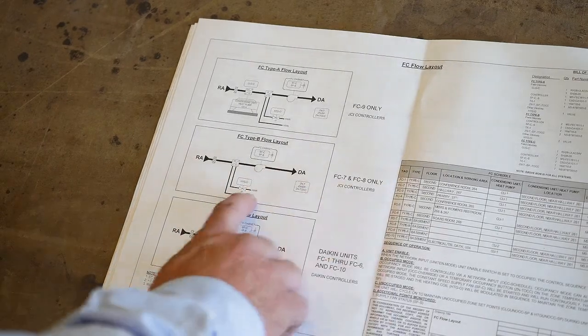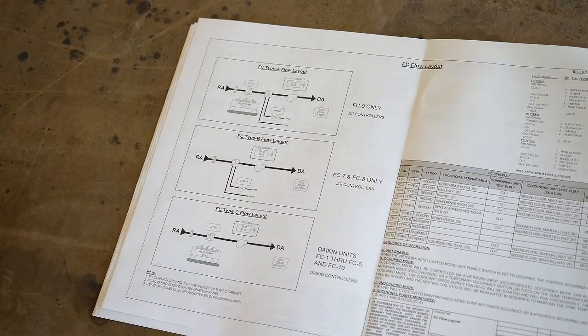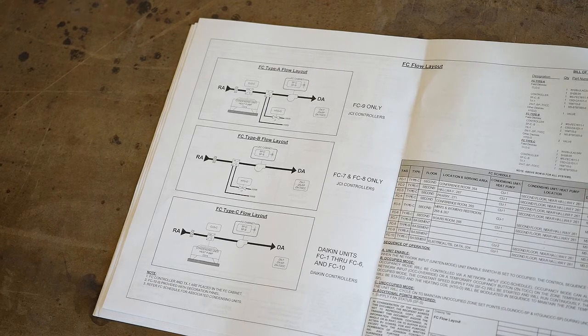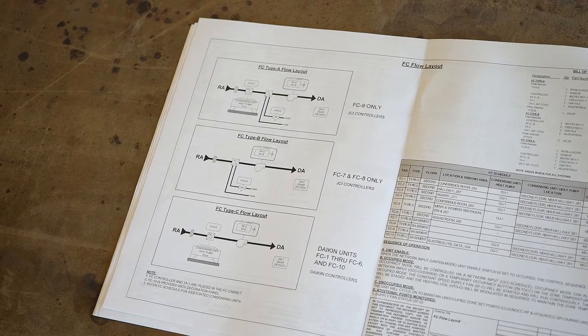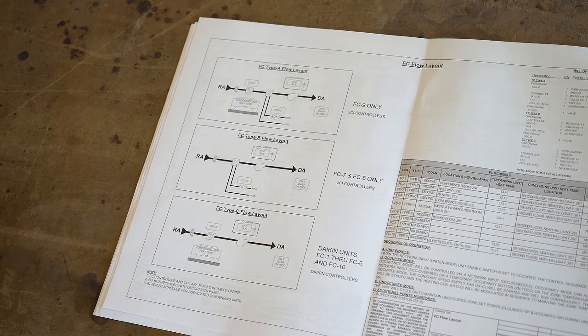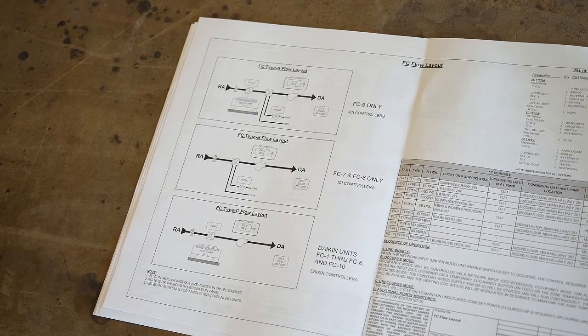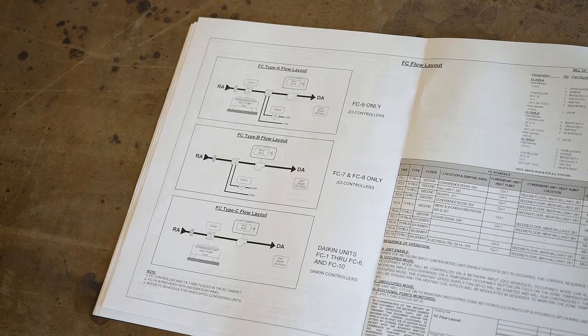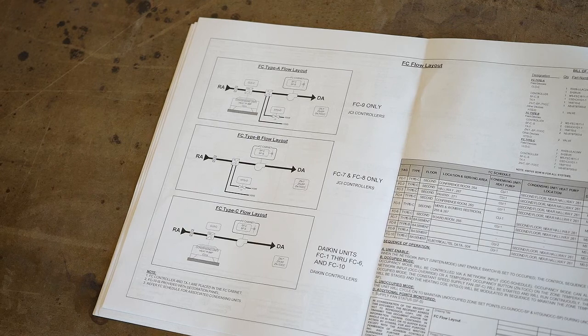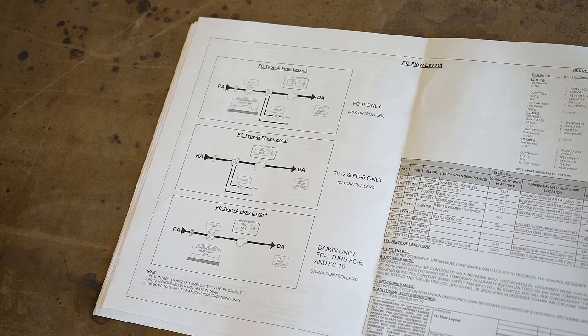we have fan coils 7 and 8 that do the main lobby and the map room, and they just have heating only. So in the map room, they have a thermostat on the wall. It looks the same as the one that's in the gift shop, and it will just turn the unit on, and it will look if it's satisfied or wants cooling. It will just run the fan. If it needs heating, then it will modulate the heating valve to heat the room up to temperature.